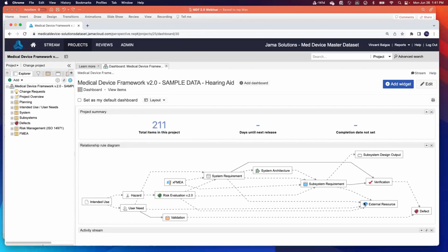The purpose of this item type is a general documentation catch-all for a lot of various traces that you may have. The most common example is associated with risk. As many of you may know, not all risk controls are requirements. So we still need a way to trace to these non-requirement risk controls. These controls could be IFUs or instructions for use, training, labeling, or packaging, etc., and may vary depending on your risk management procedures. This provides additional risk coverage traceability that provides flexibility for your organization.